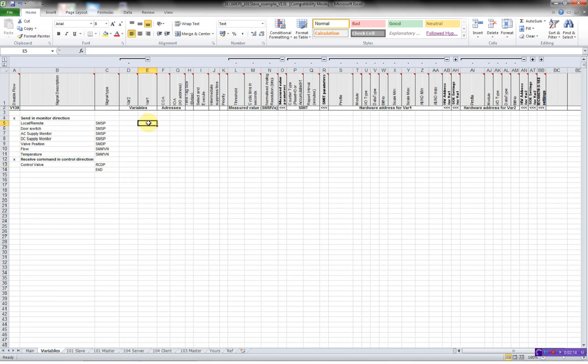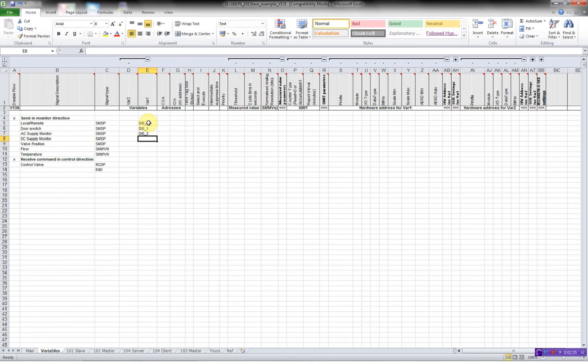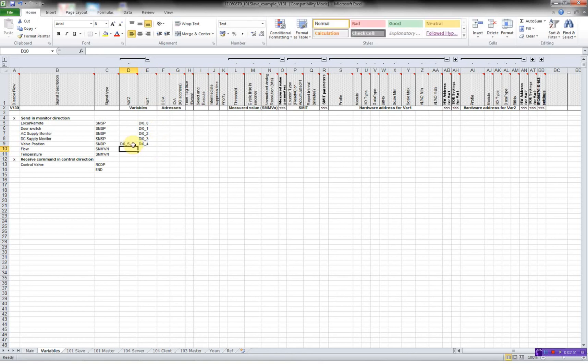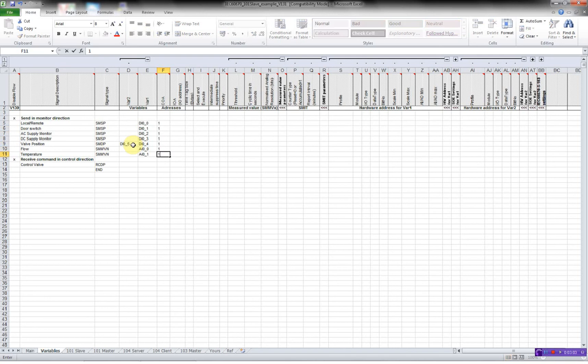Now I have to specify a variable name. In this case, I use the naming convention: digital input, module zero, bit zero. This is actually a double point, so it's using two variables. I can decide to specify the variable name myself or let the generator do it automatically. I take DI zero underscore four and make it underscore two. And this is an analog input, module zero, first analog input. Then to specify the COA, and here we have digital output, digital output one.